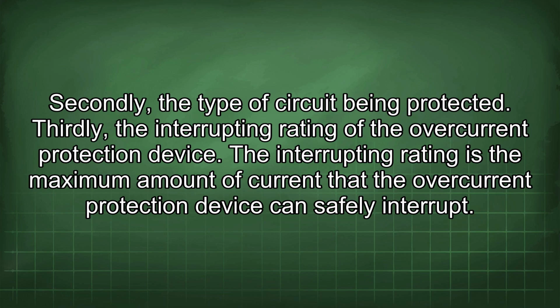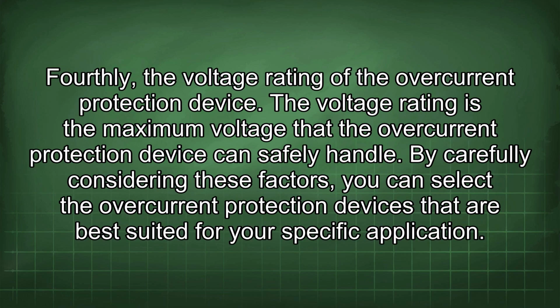The interrupting rating is the maximum amount of current that the overcurrent protection device can safely interrupt. Fourthly, the voltage rating of the overcurrent protection device. The voltage rating is the maximum voltage that the overcurrent protection device can safely handle. By carefully considering these factors, you can select the overcurrent protection devices that are best suited for your specific application.